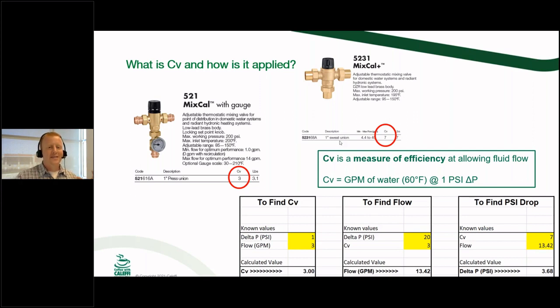The fact is that by going from this 521 up to this 5231, you're going to have a pretty big price difference. And luckily I'm the technical guy, so I don't have to talk about prices too often. But this is again where somebody's going to get themselves into trouble. They're going to say, well, why would I want to spend a lot more on this one when I can get this one for a lot cheaper? And this is where the problems come into play, is that maybe this mixing valve has the same pipe size connection, but it's not necessarily the same flow capabilities as the 5231, and that's where you're going to get in trouble. So we've got a little sheet down here, and I don't know who actually made this particular sheet. It was an Excel spreadsheet, but if you want it, make a note in the comments there. We can send it to you.